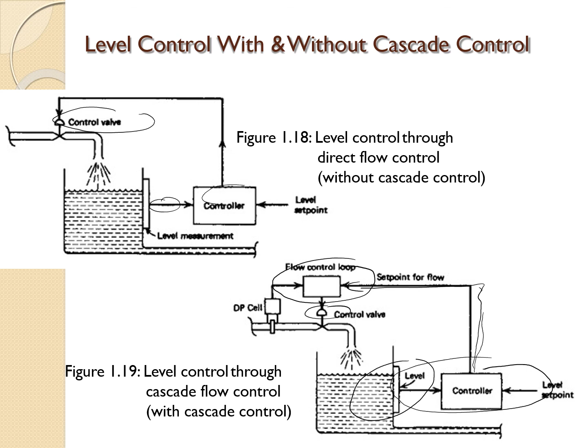If we have a cascade flow control, we must know that we have two or more controllers. So for the primary here, we have a level controller, and this level controller will send the output to the other, secondary controller, which is our flow control. This flow control will make adjustments to the control valve here in order to make sure the desired level value is met.